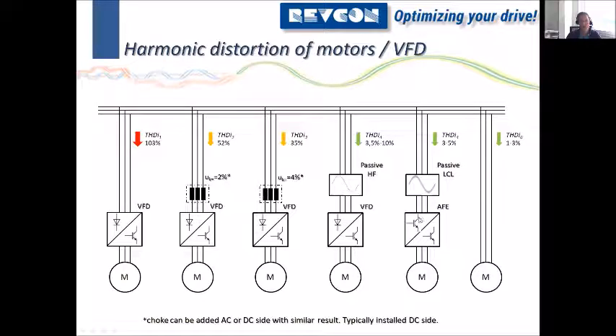As these units are high switching devices, typically in a two-level design, it will switch with about 6 to 8 kilohertz, somewhere in that area, depending on energy direction. These need an LCL filter, which is typically already inbuilt or somehow specified as mandatory by the supplier. So these are 3 to 5%. And then we have, from a harmonic point of view, the best solution, motor direct online with 1 to 3% THDI.